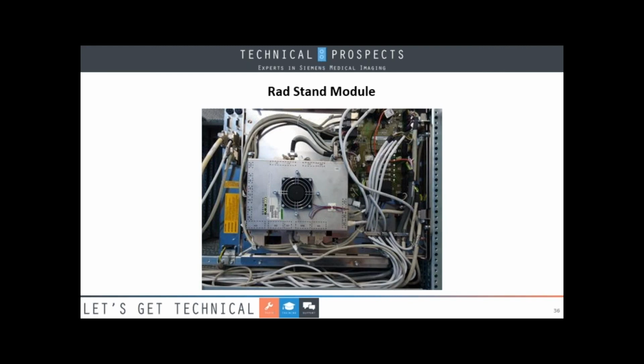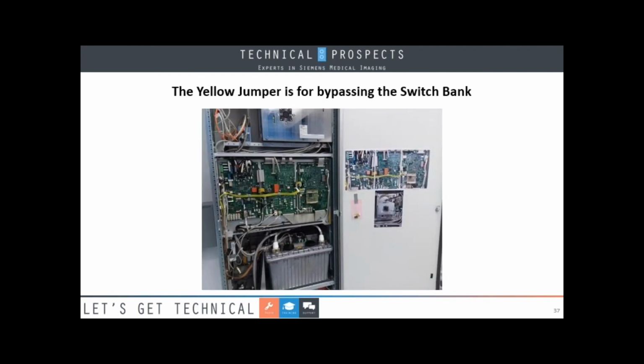So it can really be confusing when you walk in there and you don't know what it should look like. And all of a sudden you look, well, why isn't that LED on? So I really like to take a picture of that. And basically, here's what one of my cabinets looks like. There's that rad stand module or CAN communication, and there's what these boards look like. And there's that guy up there. And that's actually the jumper that's used for the digital imaging tower safety switches.